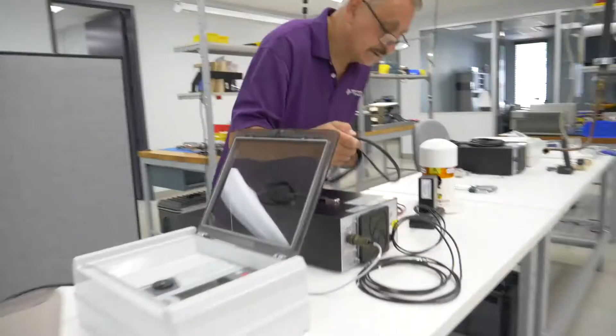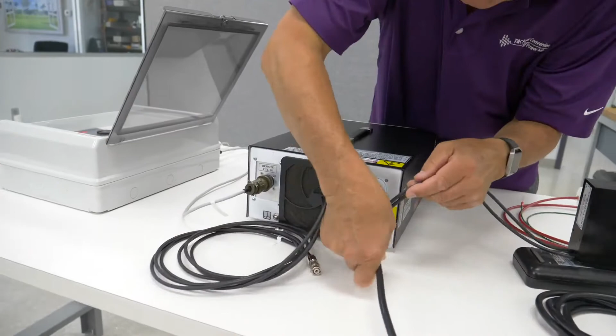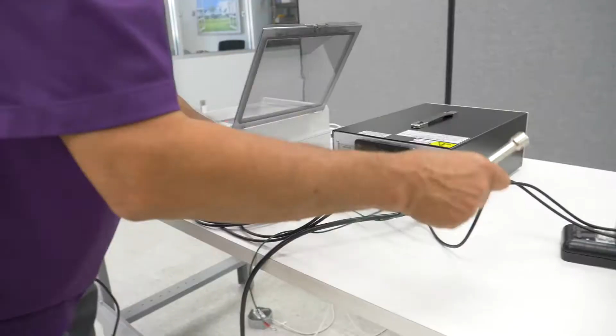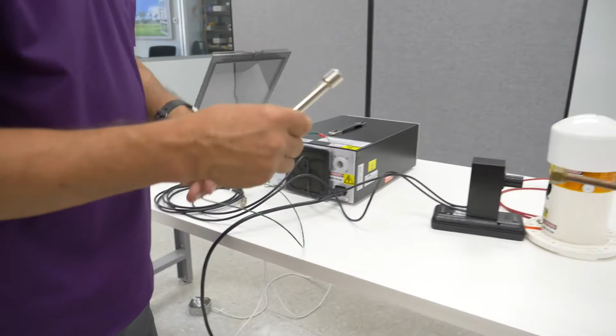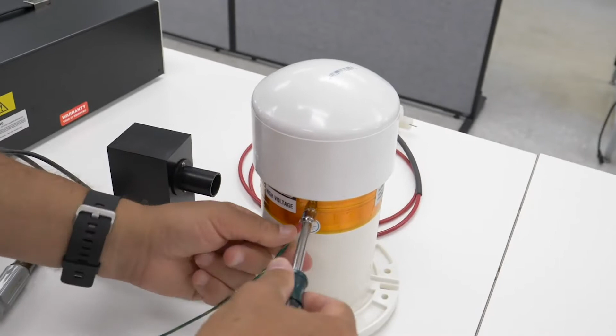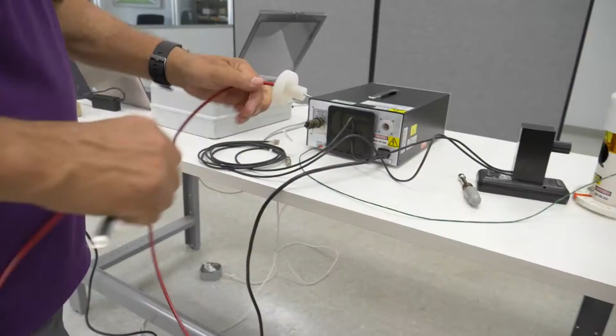The next major component, our generator, requires first of all the AC power that needs to be delivered here. There's a connection of the grounding wire, which should be connected to the terminal on the back. This is American standard 1/4 by 20. The other end should be connected to the grounding frame of a lamp conveyor on the production floor.